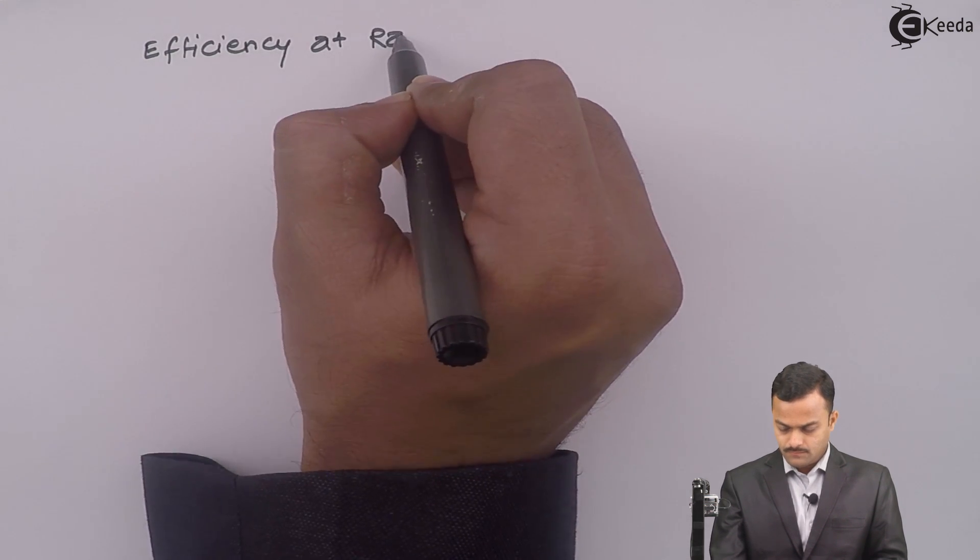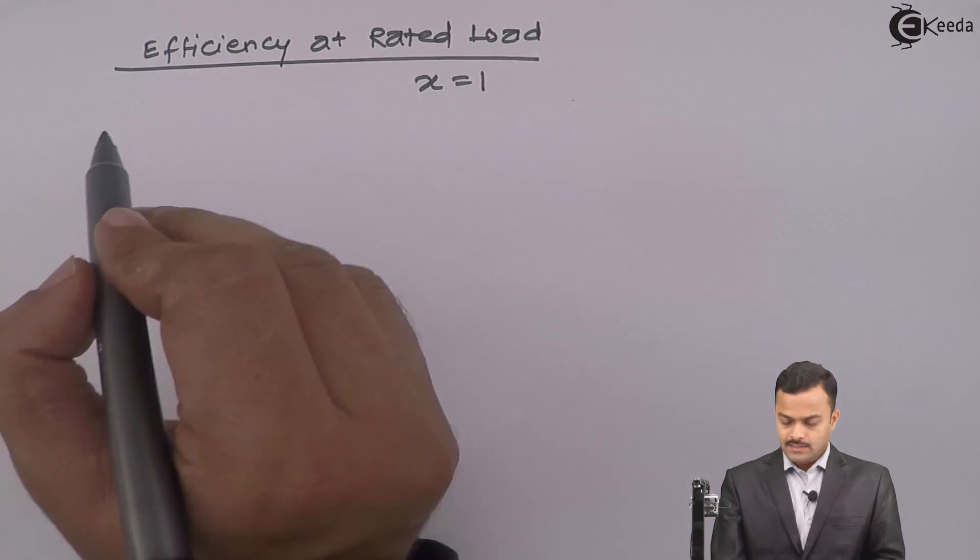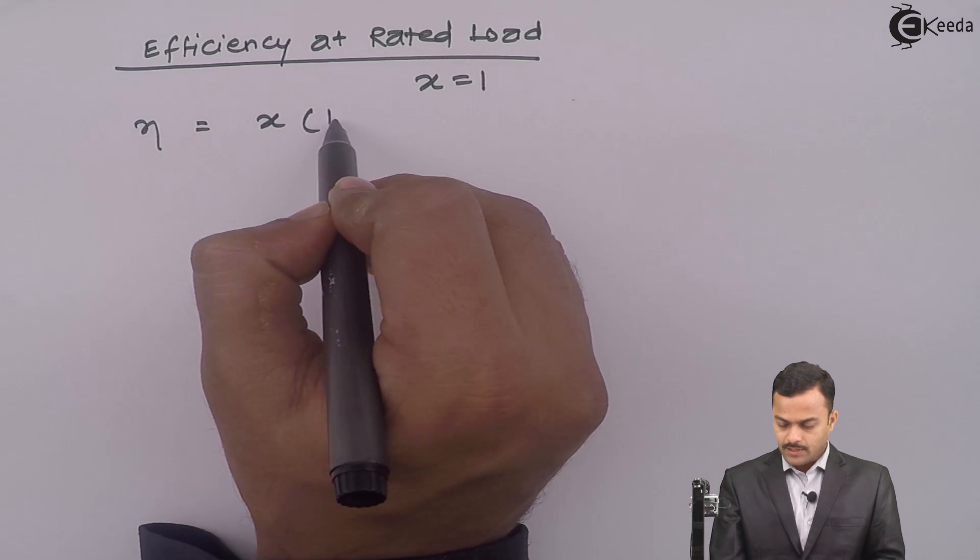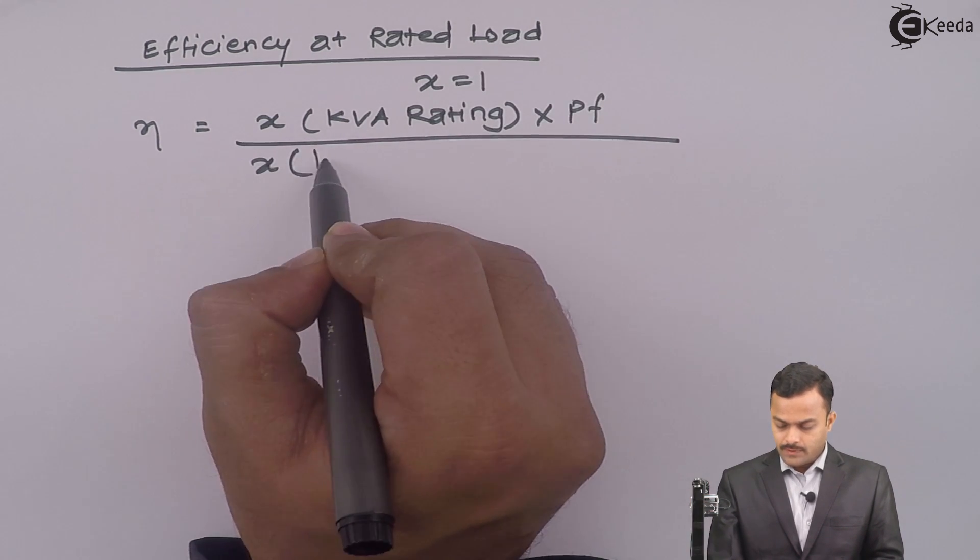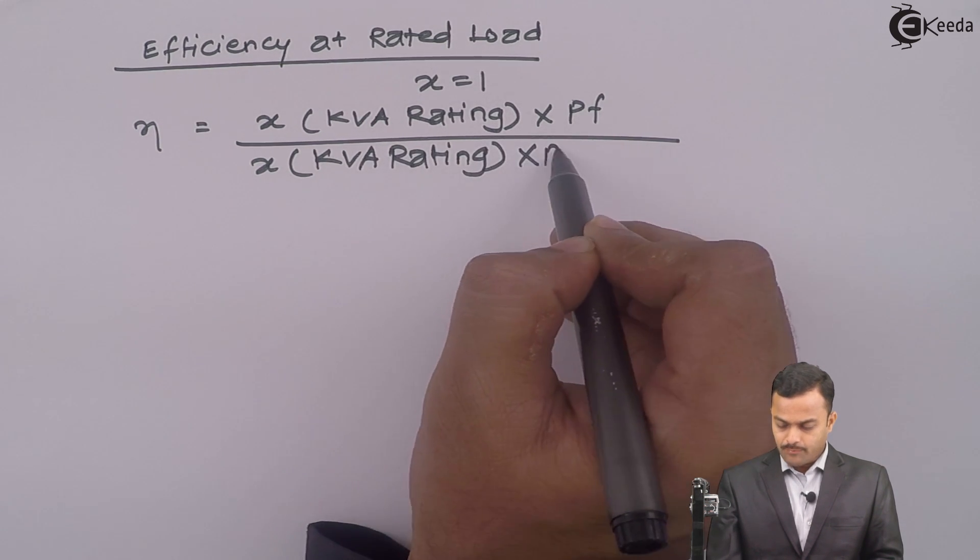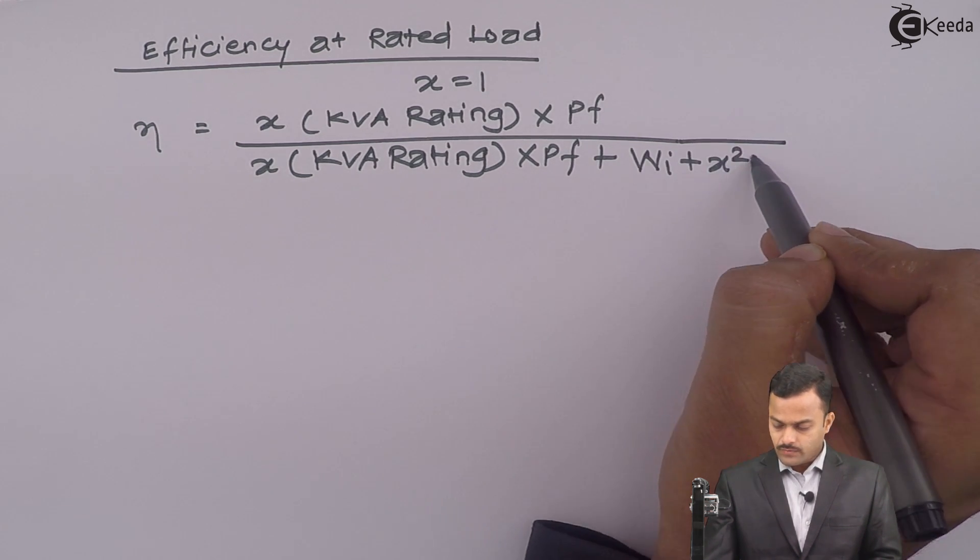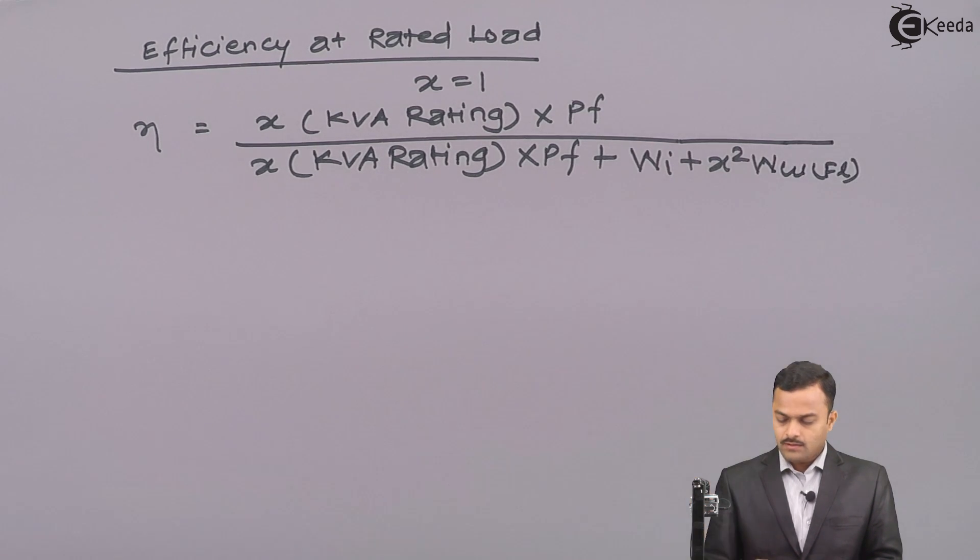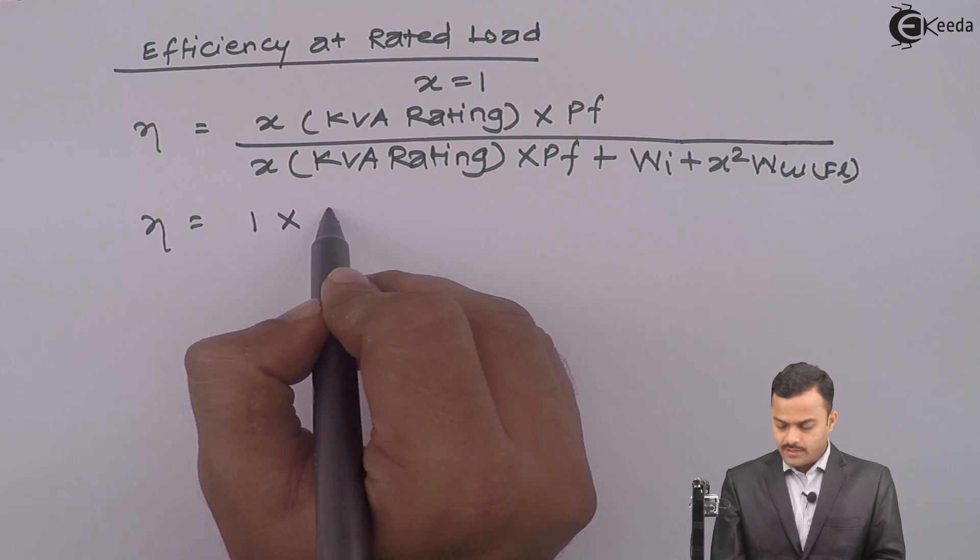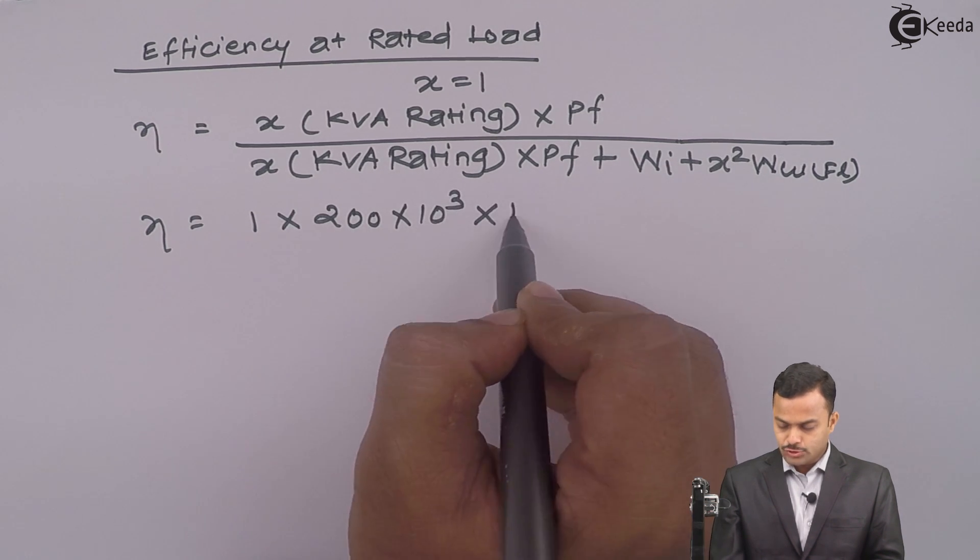So in the first case, we have to find out efficiency at rated load. Rated load means X equal to 1 and so the formula is X multiplied by KVA rating multiplied by power factor divided by X into KVA rating multiplied by power factor plus iron loss plus X square WCUFL. All the values are known to us.